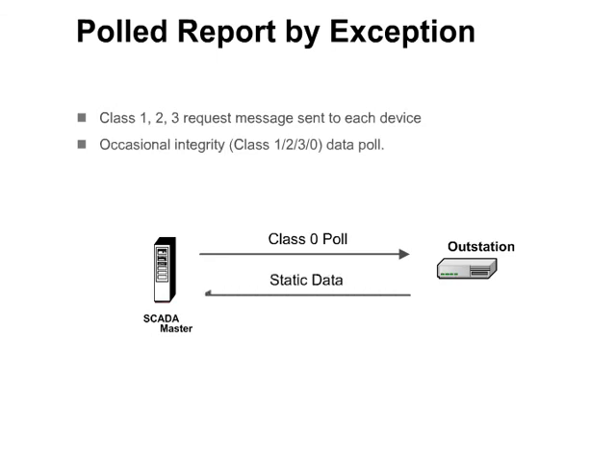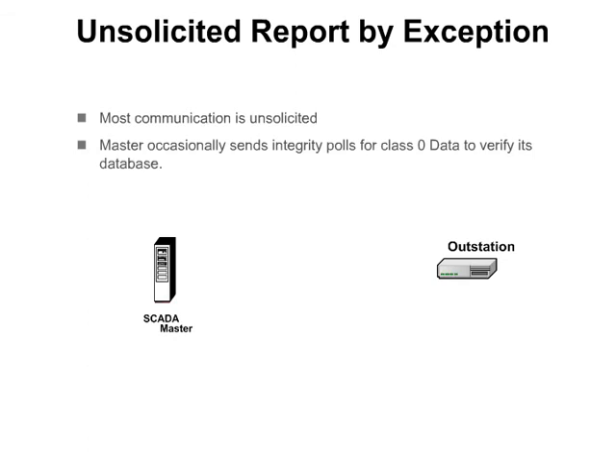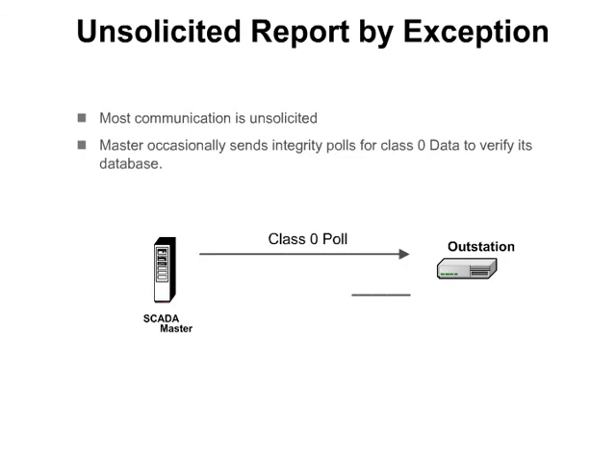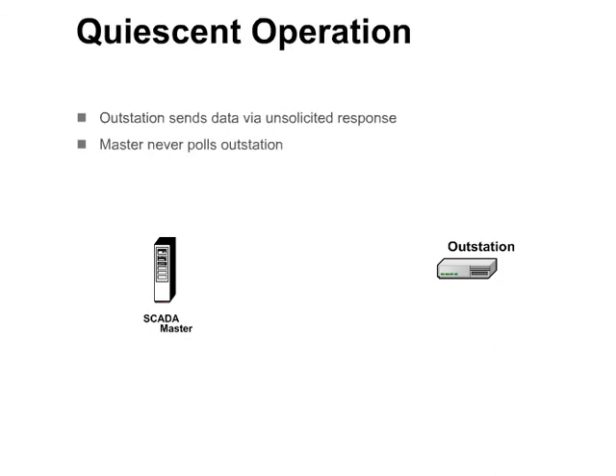With unsolicited report by exception, the outstation sends unsolicited responses containing changes or events. This allows the master station to be updated on events without the need to poll. However, it requires some type of collision avoidance mechanism if multiple outstations are sharing the same media. In addition to receiving unsolicited responses, the master station occasionally sends integrity — class 1, 2, 3, 0 — polls to verify that its database is up-to-date. With quiescent operation, the outstation only reports data via unsolicited responses and the master never polls the outstation. This method is most commonly used in point-to-point networks — for example, in dial-up applications in which the outstation dials into the master to deliver its unsolicited responses.